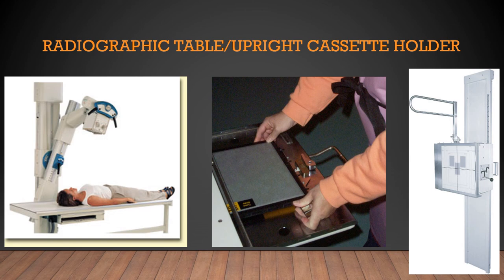The upright cassette holder also has a bucky inside it. In some situations you can remove the grid inside the upright cassette holder by opening the facing of the cassette holder. However, be careful — if it gets put back in backwards, your x-rays will be very poor. Try not to remove a grid unless it is specifically needed to place it over top of an image receptor or on top of a cassette.